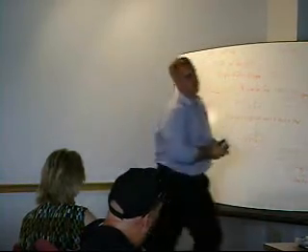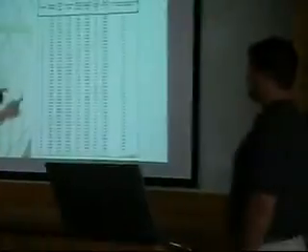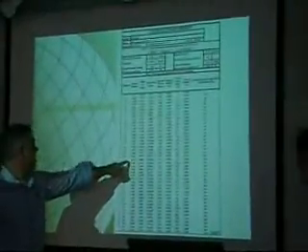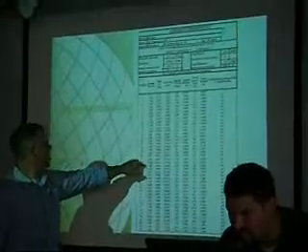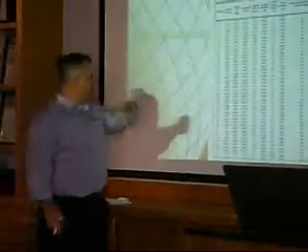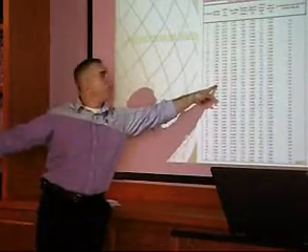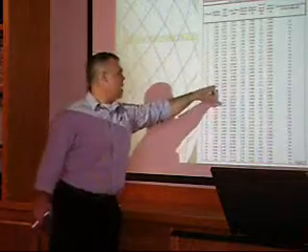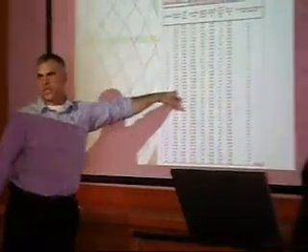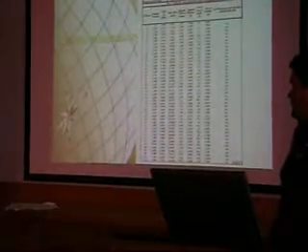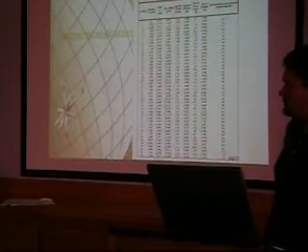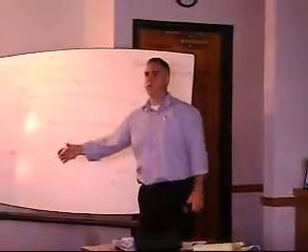It's a fudge factor. Here's why. I know you can't see it. 4.899 is the first column. This is going to equal, in this case, 4.55. Everybody said that's a fudge factor. This spreadsheet comes from a guy who's got a little engineer calculator. At 20 holes, the real delivery head, when you set it for the end at 3.5, the real delivery head is 3.8, when you engineer it out with a calculator. Both these manuals give you a fudge factor to get that. Almost, not quite, but almost another foot ahead, built into the first fudge factor.